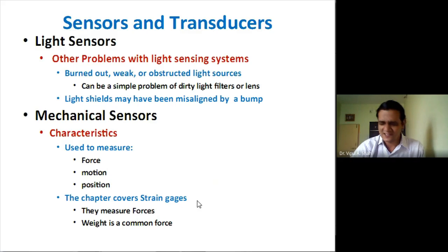The purpose of the strain gauges is that a specific wire, a specific material, is used as the strain gauge material. This wire will have elongation or expansion, or contraction, as and when you apply certain forces. When the forces are in opposite directions towards the outer way, it is the expanded condition.